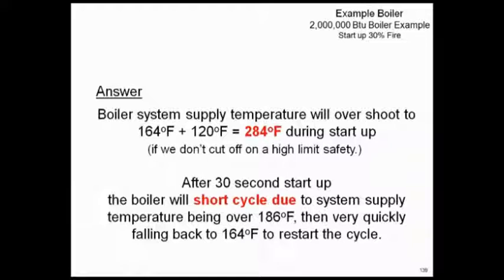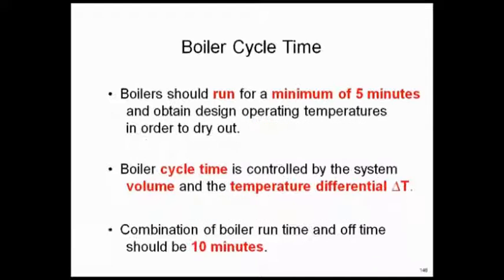This is a major issue that people have really not picked up on. So, boiler cycle time. We talked about cycle time and startup. It's two different issues really that tie together. You've got to get the idea of the fire rate at startup, that minimum flow. Now I'm over the short cycle of my boiler. So let's look at, we are modulating the boiler down to whatever the minimum fire rate may be. What are your goals with a boiler to get long life out of it?